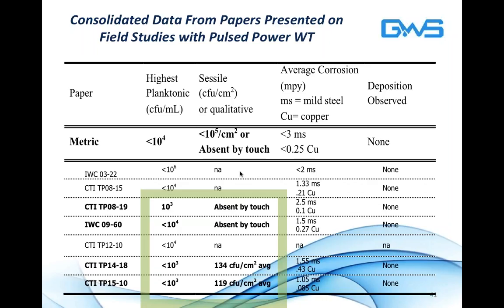I'd like you to look at a couple of papers going back into 2008 all the way up to 2015, where a qualitative examination of biofilm, the sessile bacteria, was absent by touch in some earlier studies. Later in 2014, 2015, those biofilms were enumerated to be very, very low, under 150 colony forming units per square centimeter. If you look above, the common metric is 10 to the 5th per centimeter squared, or absent by touch. In the cases we're seeing here with pulse power water treatment and Wave, there's very good control of the biofilm, as well as very good control of what we call planktonic, or free-floating, bacteria.